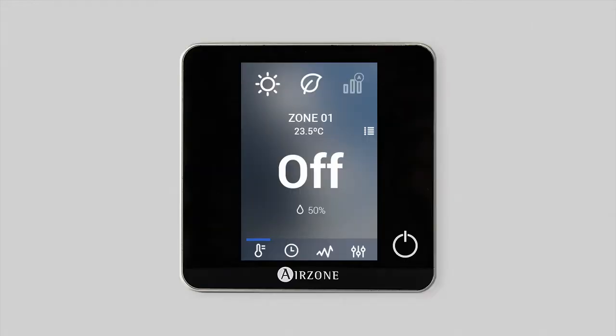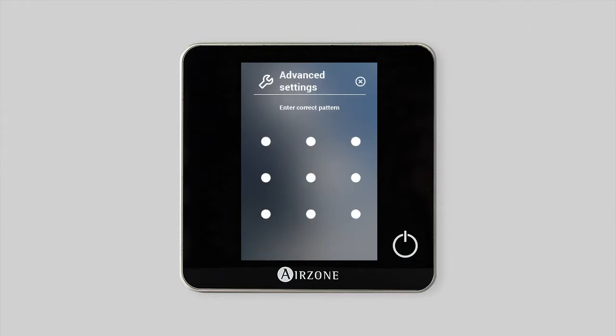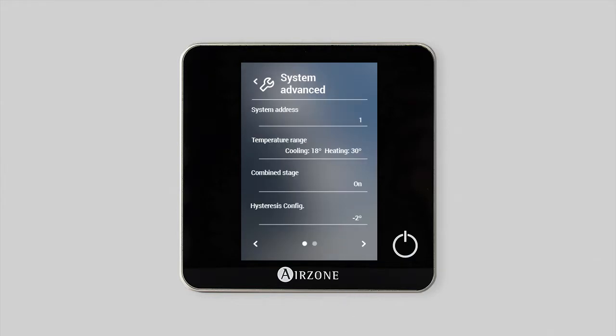Proportionality: the Airzone system offers the possibility of controlling the gradual opening of the dampers in order to offer more gentle variation in the airflow supply. This option is accessed from the system advanced settings menu on the master blue face thermostat.